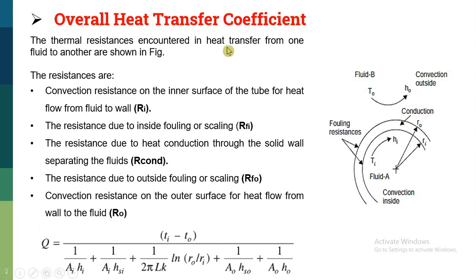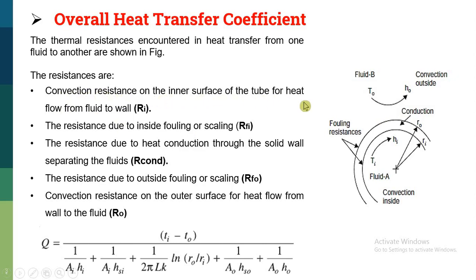Now let us understand this diagram. This is a tube which separates the hot fluid and cold fluid. If hot fluid is passing through the tube and cold fluid is present outside the tube, there are different kinds of resistances which may occur. Fouling may occur from inside as well as outside. The first resistance is convection resistance on the inner surface of the tube — heat flowing from the fluid to the wall — which is called RI.